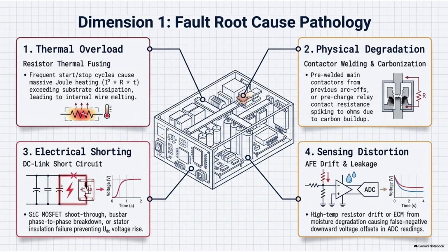It's essentially lightning inside a plastic box, a localized lightning strike. And the temperature of that plasma arc can exceed 10,000 degrees Fahrenheit. It's identical to the physics of an arc welder used in heavy construction.